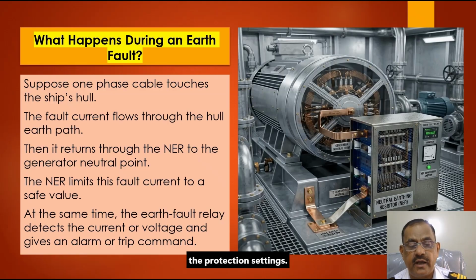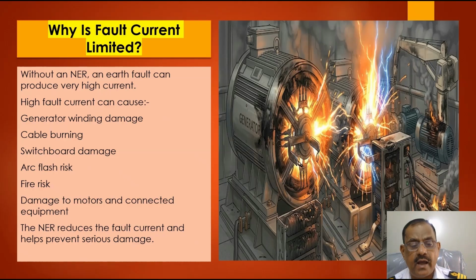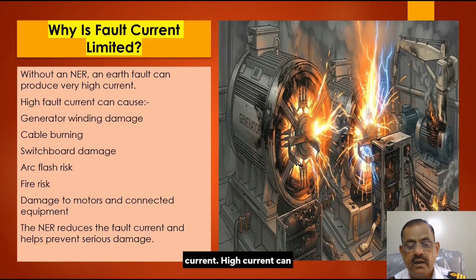Without an NER, an earth fault may produce a very high current that can damage generator windings, cables, switchboards, motors and other electrical equipment. It can also increase the risk of arc flash and fire. The NER reduces the fault current and helps prevent serious damage.